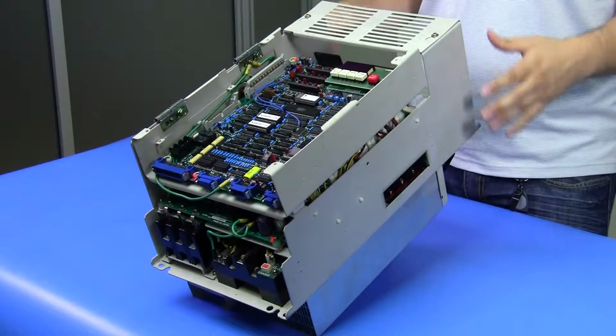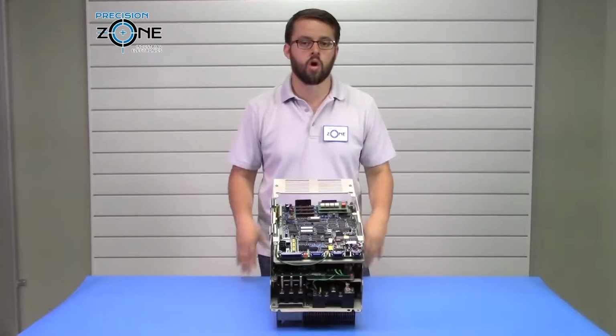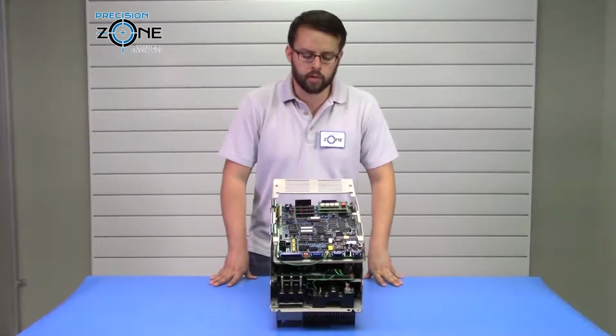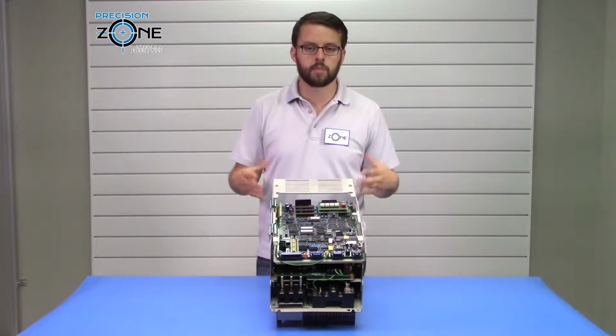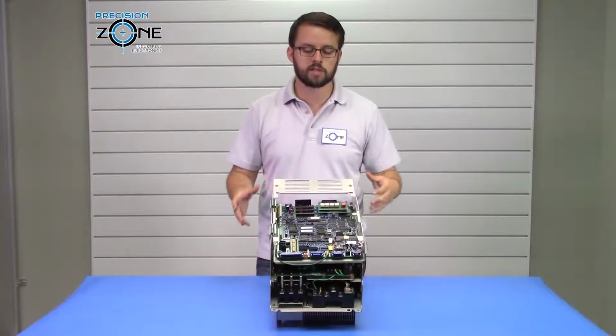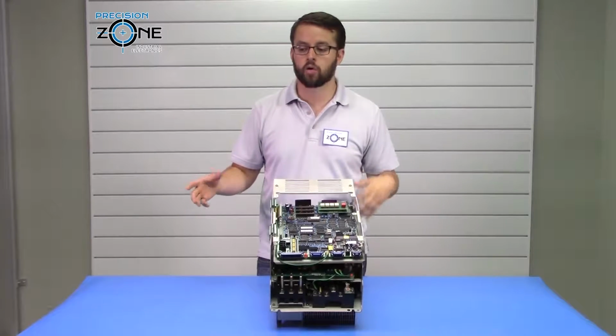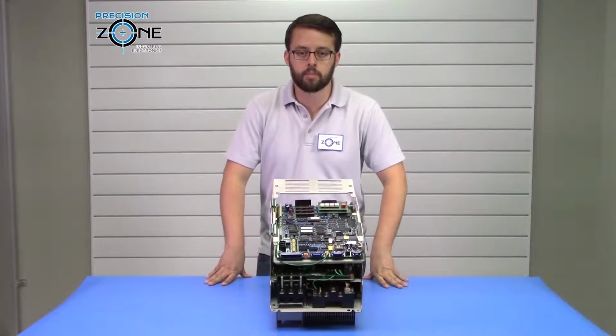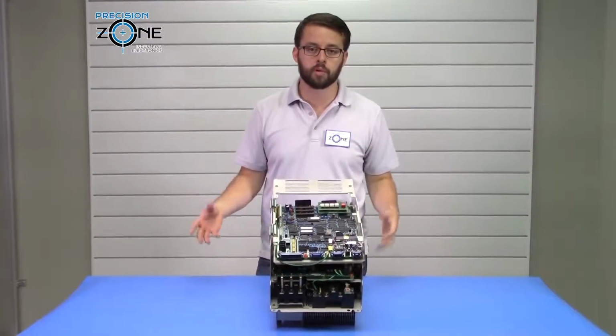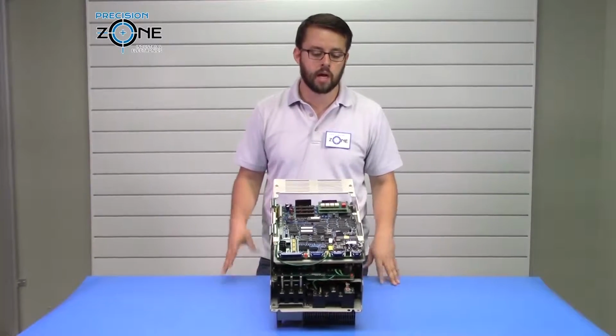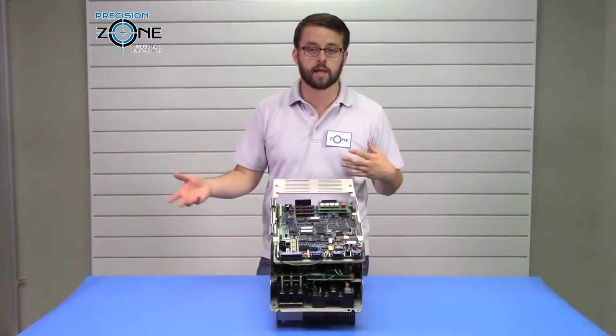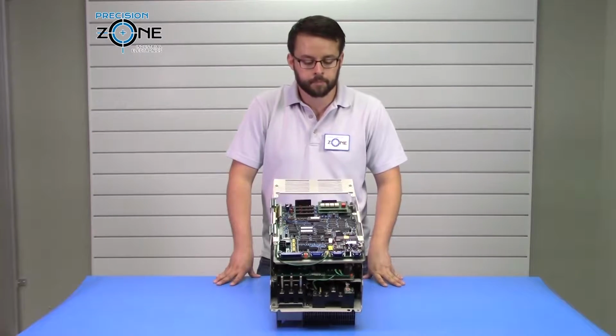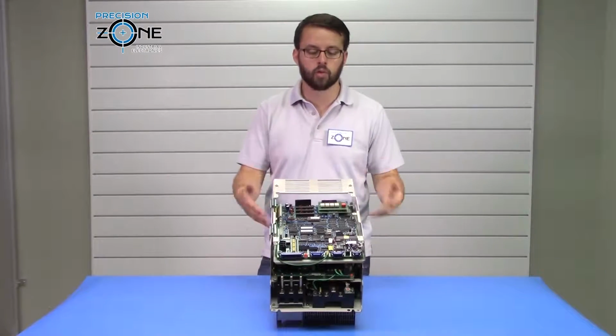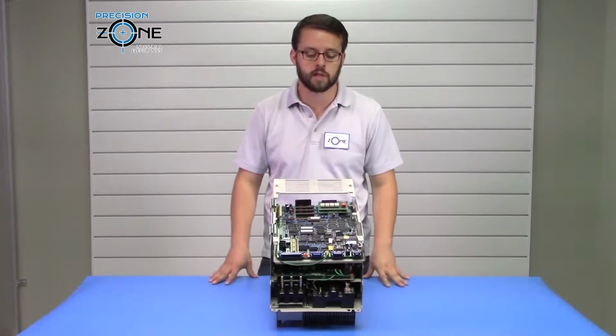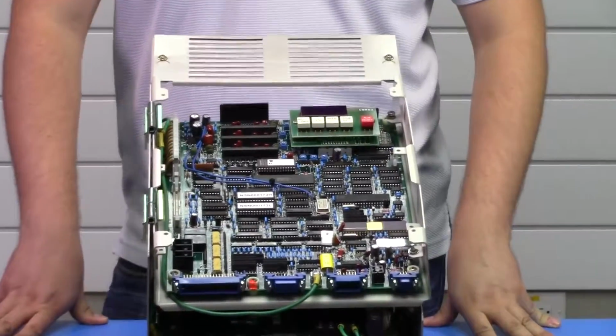Other issues that you can get are overload or overheat, or OHL. All those are going to be load related alarms, and in those cases you want to verify the integrity or the conditions in which your motor is operating. If it's being properly cooled, if the fans are working, those are things that can trigger the alarms. You also want to verify that the cooling on the drive is done properly. That can cause an overload issue as well.